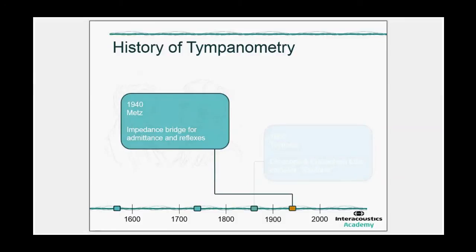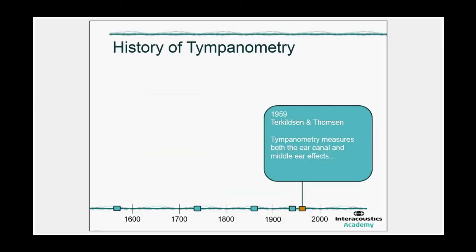The first tympanometer was built in 1940 by Metz. It was an impedance bridge which could measure reflexes and the compliance of the middle ear. He did not use pressure yet. It took a few years until around 1959, 1960, when they found out that adding a pressure sweep is beneficial, because by moving completely up to the positive pressure, you get ear canal properties only. And then you can separate ear canal properties from the middle ear properties that we are interested in.